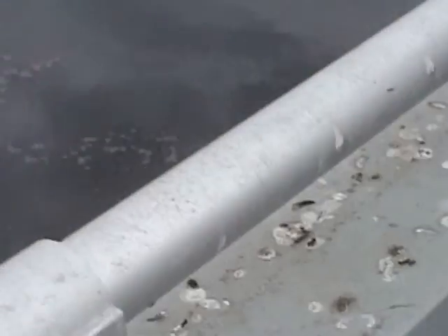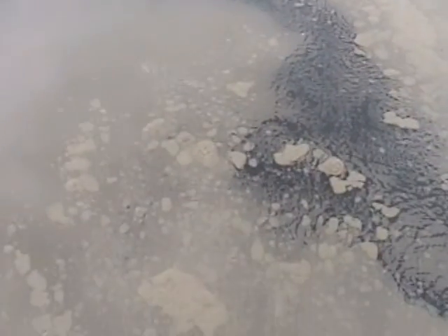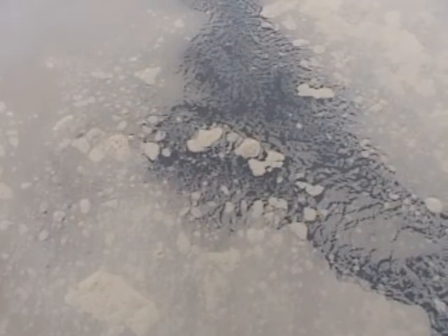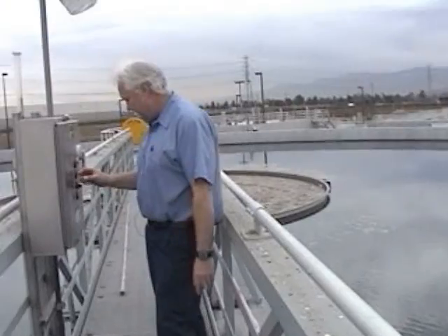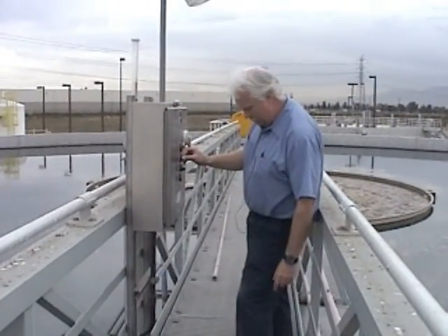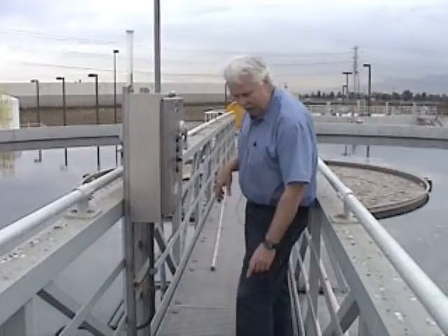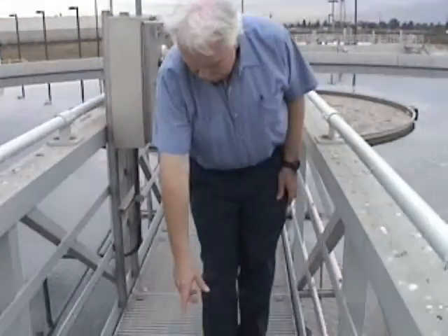And what I do when I'm out here in the field and I see a little bit of a layer, like a film like we have here today, is I'll put the ducking skimmer into hand, then I'll lower it just a tiny bit and stop it, just enough to pick up the little bit of film that's on the surface of the water. You can see it flowing over there. And this isn't too bad.